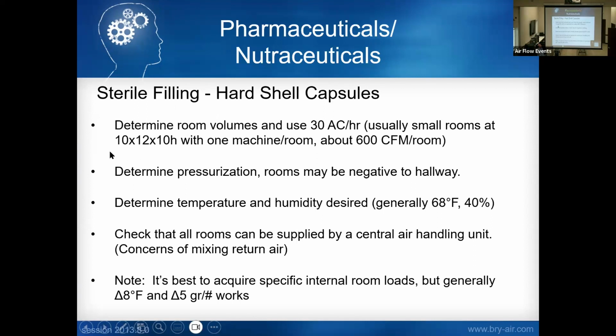Hard shells, typically those are about 30 air changes an hour. Pressurization, these rooms are typically negative to a hallway. Simply we see about 68 degrees, 40% RH in those room conditions. Again, they're concerned about mixing air, so how we do the ductwork, everything's very critical.